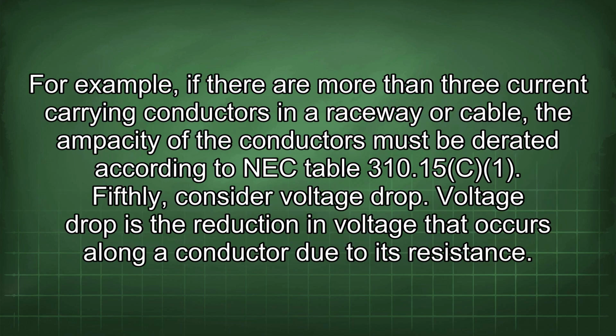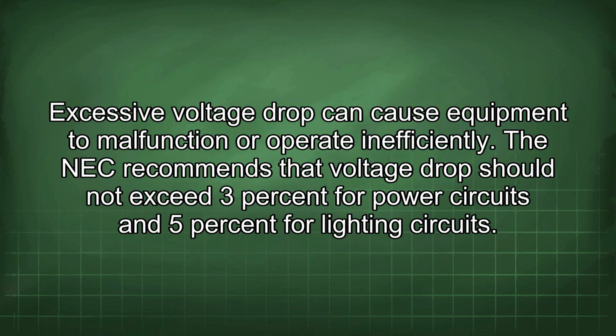If derating factors apply, you may need to select a larger conductor size to compensate for the derating. For example, if there are more than 3 current-carrying conductors in a raceway or cable, the ampacity of the conductors must be derated according to NEC table 310.15. Fifthly, consider voltage drop. Voltage drop is the reduction in voltage that occurs along a conductor due to its resistance. Excessive voltage drop can cause equipment to malfunction or operate inefficiently. The NEC recommends that voltage drop should not exceed 3% for power circuits and 5% for lighting circuits.